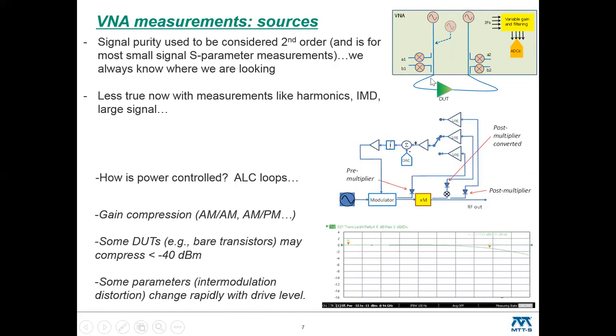The sources themselves are a little more interesting in that historically in the network analysis universe, signal purity was not the highest priority. For small signal S-parameters, that makes a certain amount of sense, since you know what frequency you're measuring at and you're not likely to put the DUT into some unknown operating state. But that's been changing as a wider variety of measurements are being demanded of the instrumentation, like harmonics and intermodulation distortion. Also, if you're driving this device in a quasi-linear way, then too much harmonic energy can alter its bias point and cause other issues.